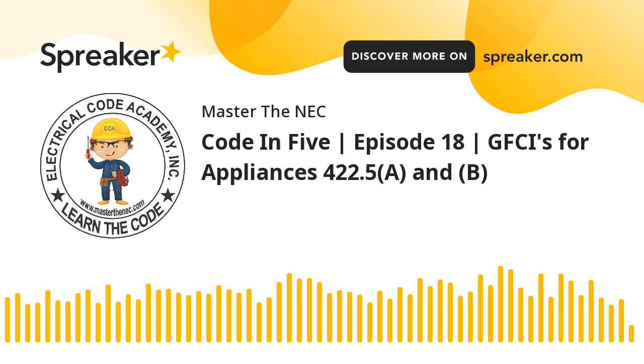Then you've got D, and the D is specific appliances. It used to be just dishwashers, and that only applied to residential dishwashers. That's been moved over to 422.5. So we have a location here, which we like to call a placeholder, that's actually sending you to 422.5. Then you've got E, which is equipment requiring servicing. GFCI protection shall be provided where the receptacles are required by 210.63, the servicing equipment's dedicated space. And then you have outdoor outlets. When we say outlets, we're not just talking receptacles, but outdoor outlets in general, a point where you take power from it. So you have all these rules, but what we want to focus on is 422.5.